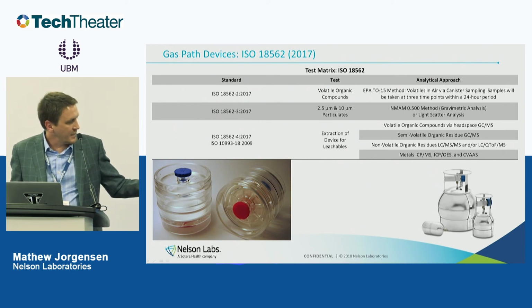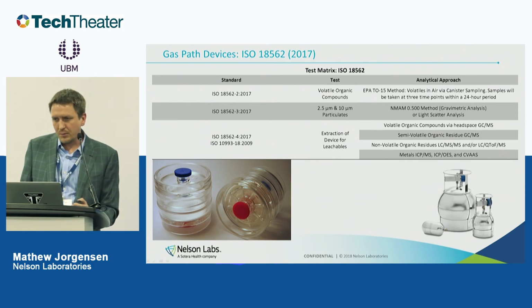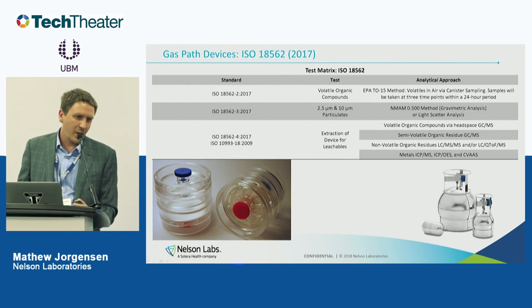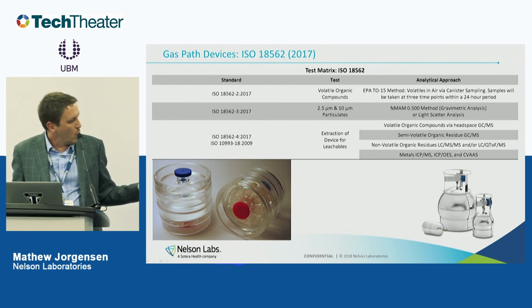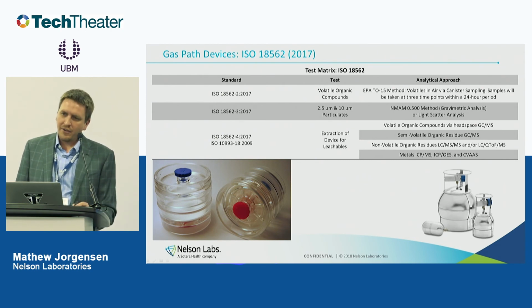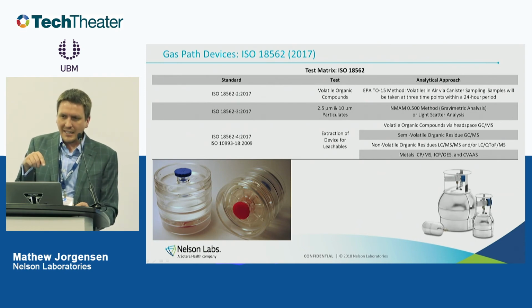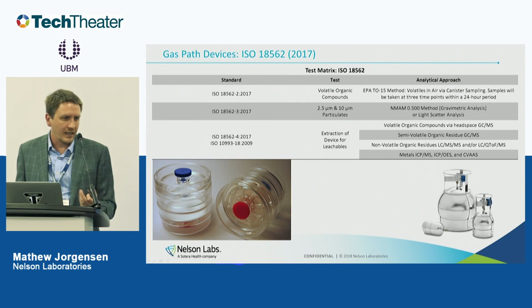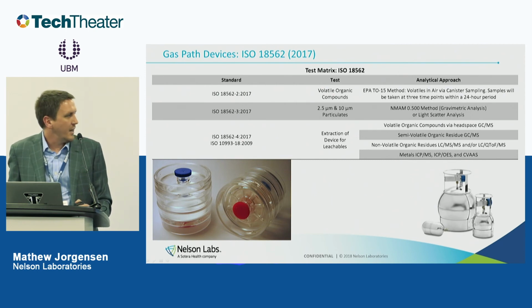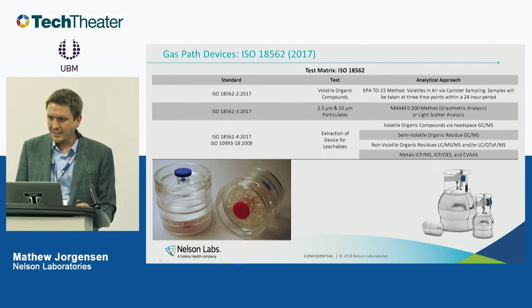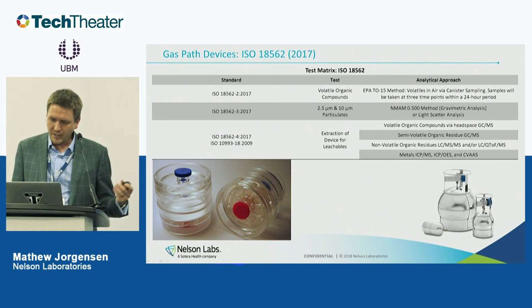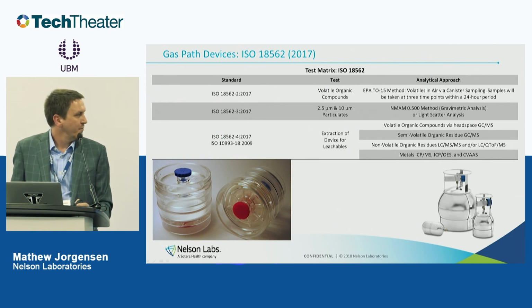For the particulates, the standard gives two options. You can either use a filter and measure it by weight, which is a strategy that we've done before, or you can use dynamic light scattering. You have a laser across the gas path, and depending on the size and number of particles, the laser scatters more or less, so you can measure the amount of particulates that way. So this is what you should do for gas path devices. If you're going to be submitting in Europe, you're going to need to comply with this.